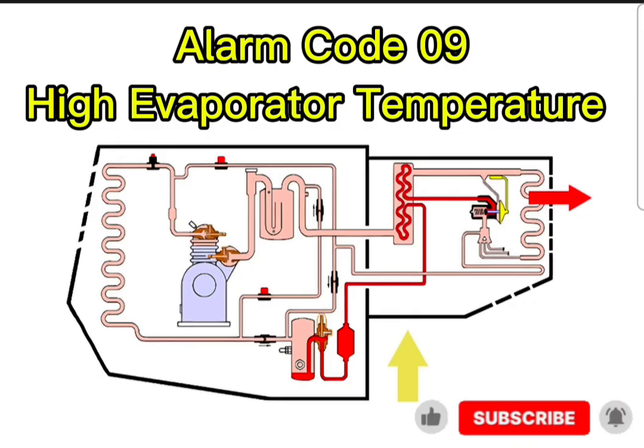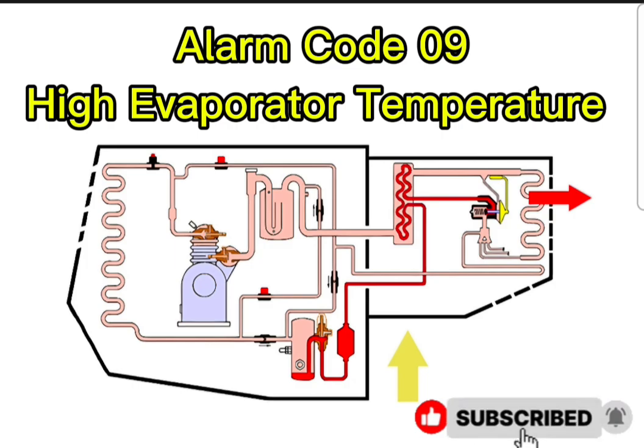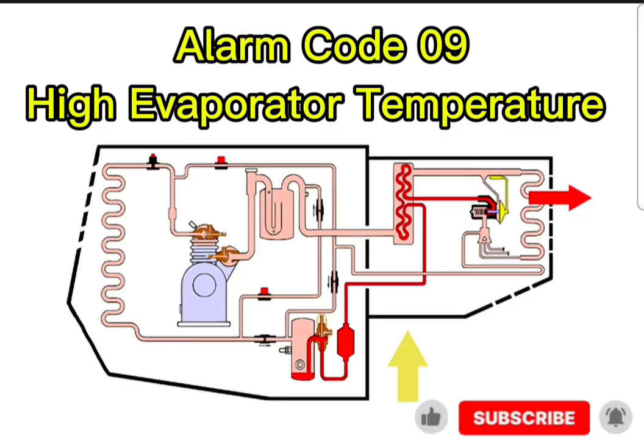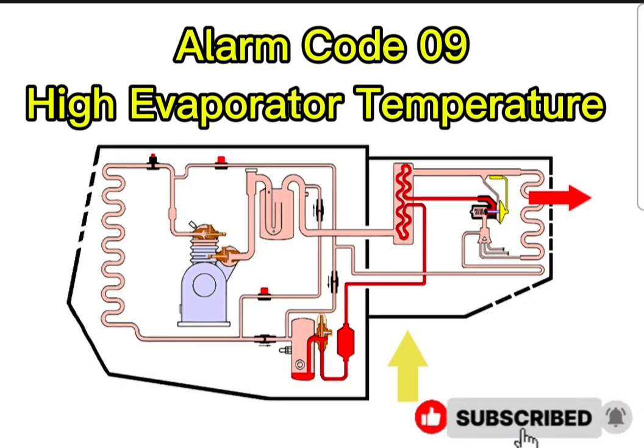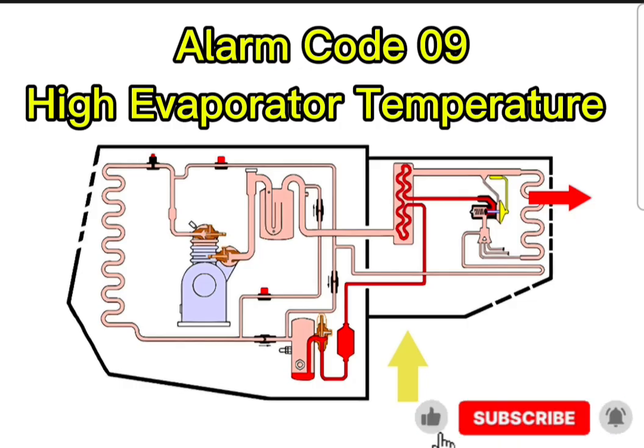It is actively demanding human intervention. Now, here is where I get a little hung up on the engineering choices. The manual tells us exactly where this temperature is being read. The sensor responsible for triggering this massive system-wide shutdown is located on something called the evaporator coil suction header plate. That's a mouthful. First of all, paint a picture for me. Where is that and what is it doing?